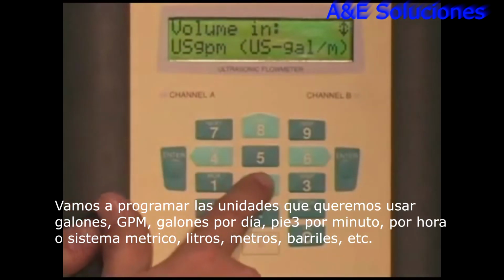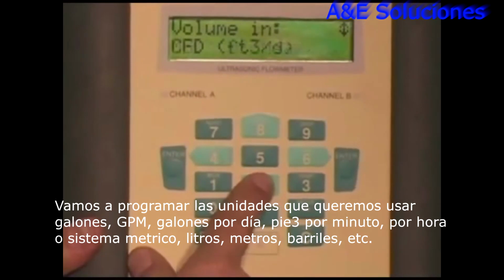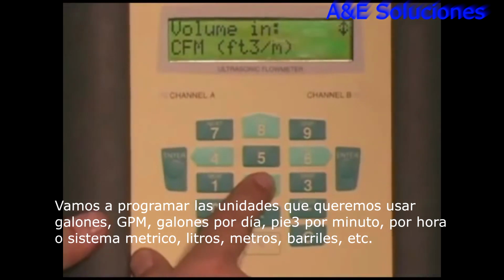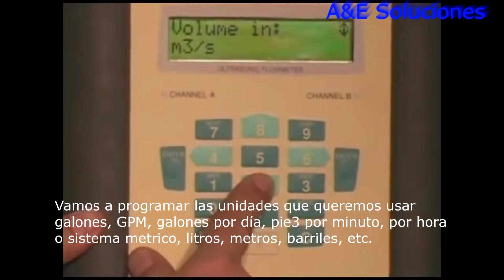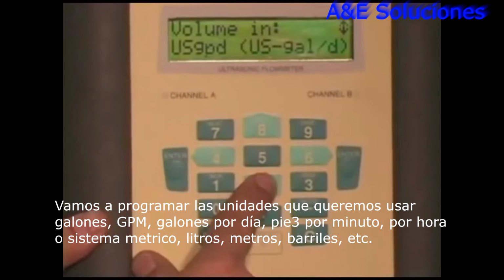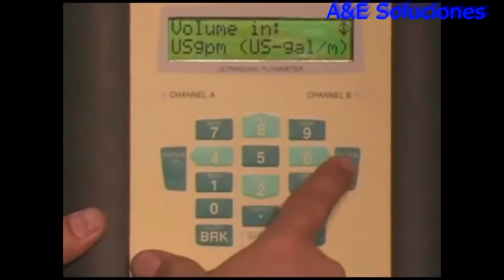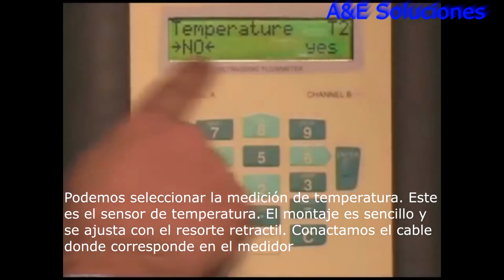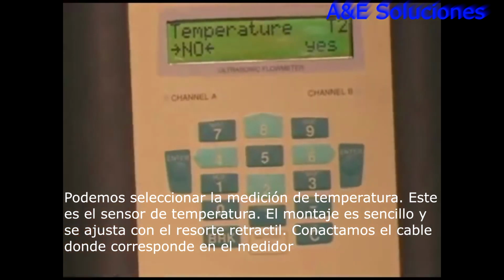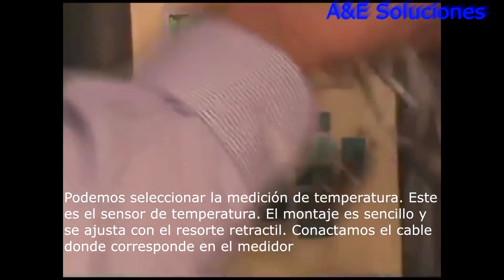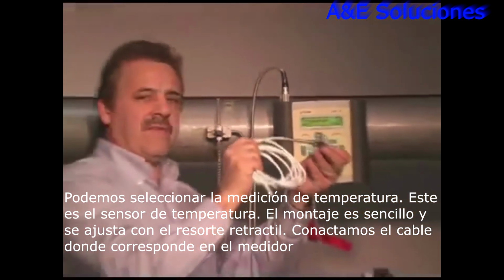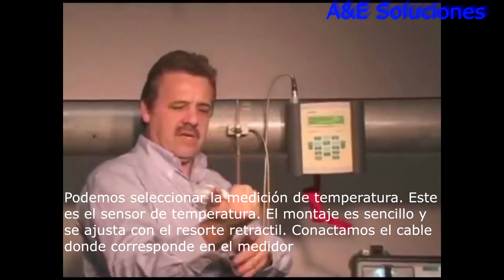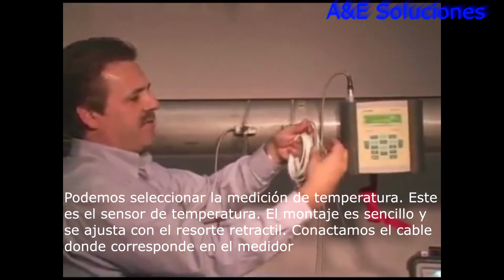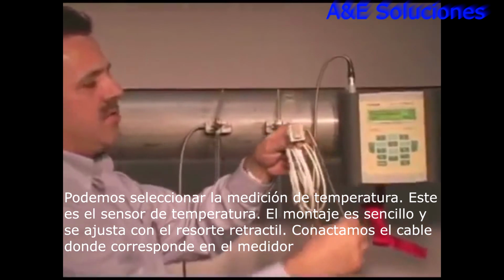We can choose the units that we want to measure in: gallons per minute, gallons per day, cubic feet per hour, and so on, metric units, liters, barrels, and back to gallons per minute. We can choose to have temperature measurement. Now this is a temperature sensor that we have, just pulled out of our case, and this is a surface mount type temperature sensor that goes with our portable meter.